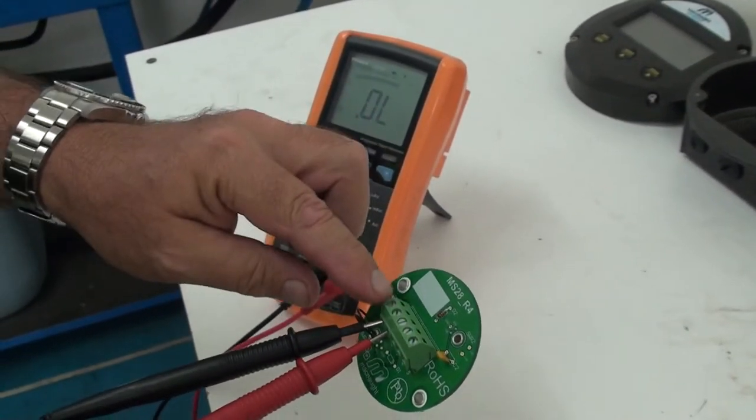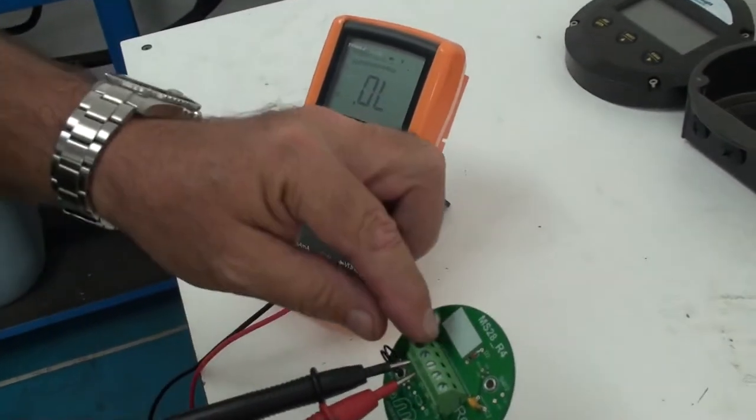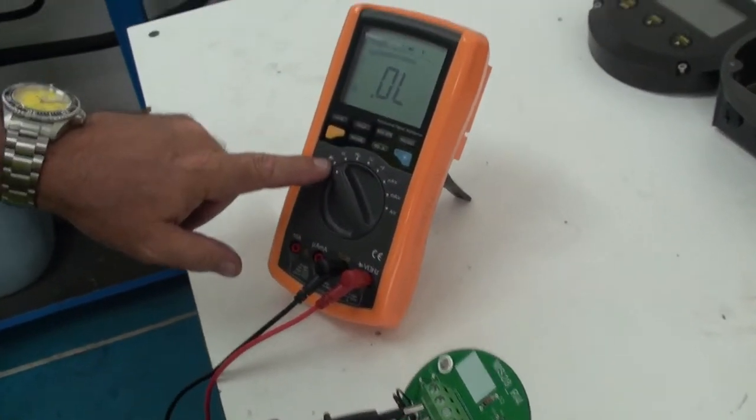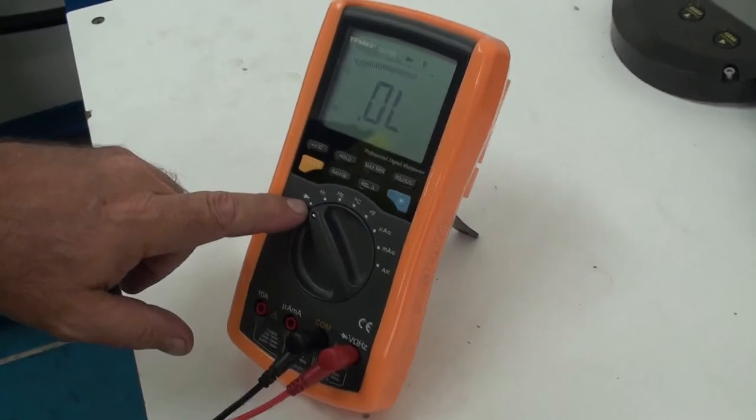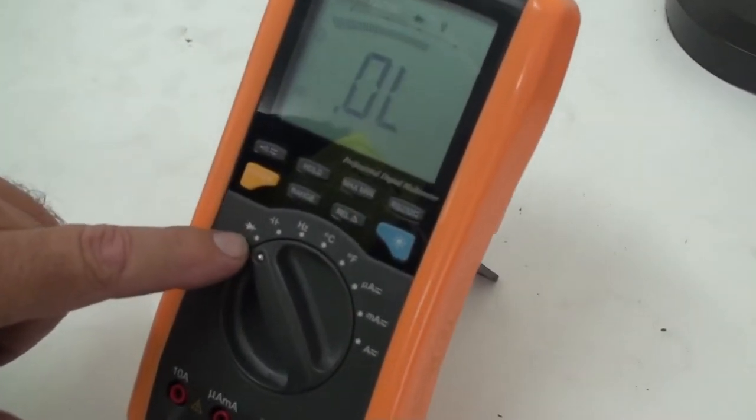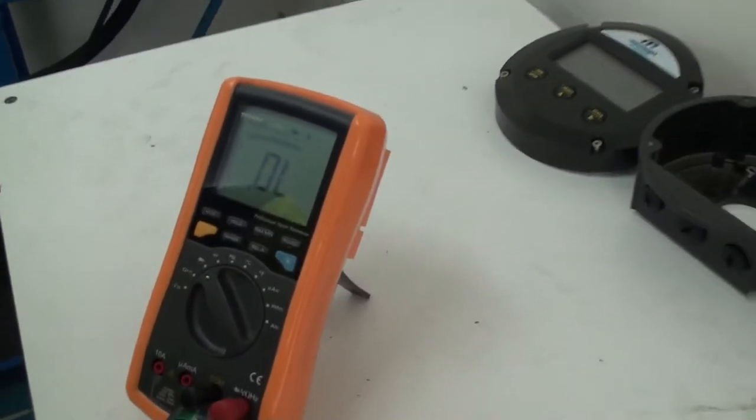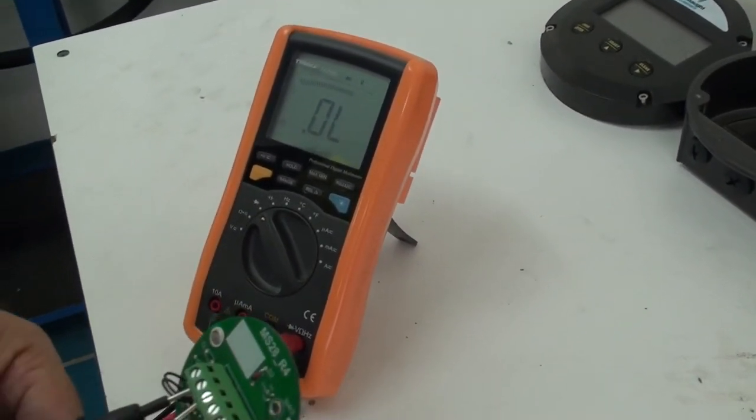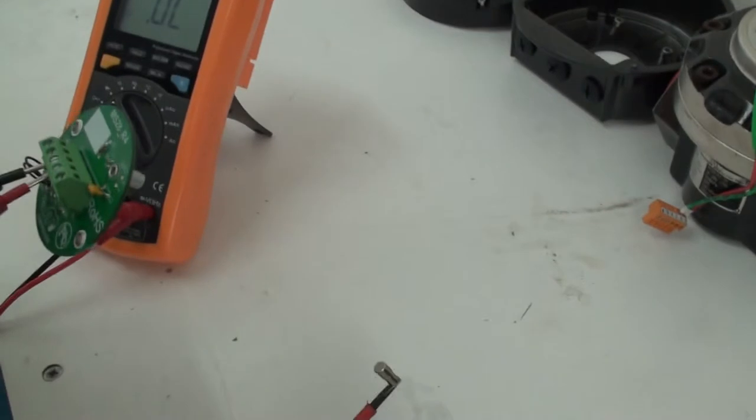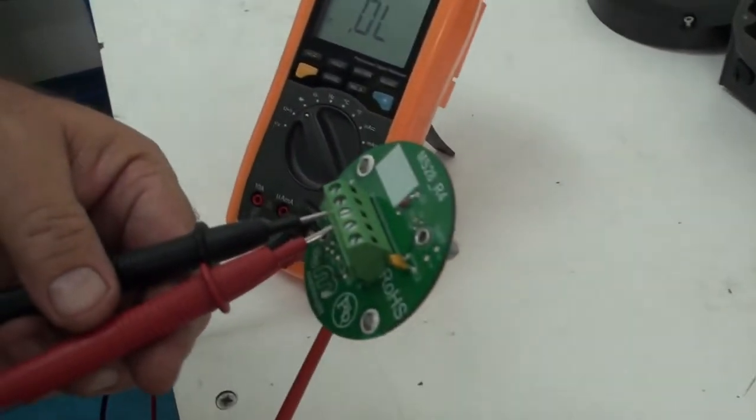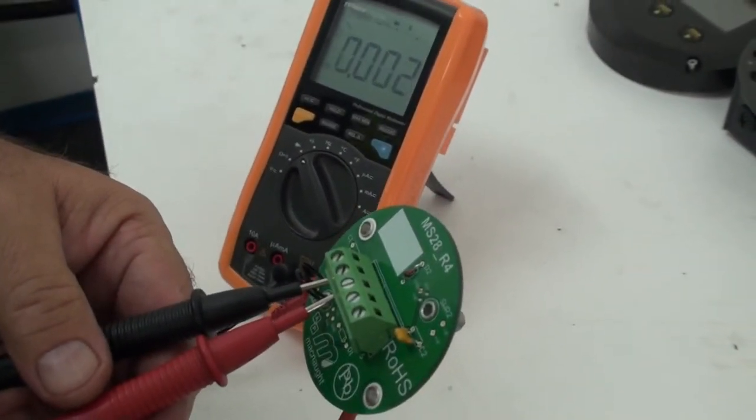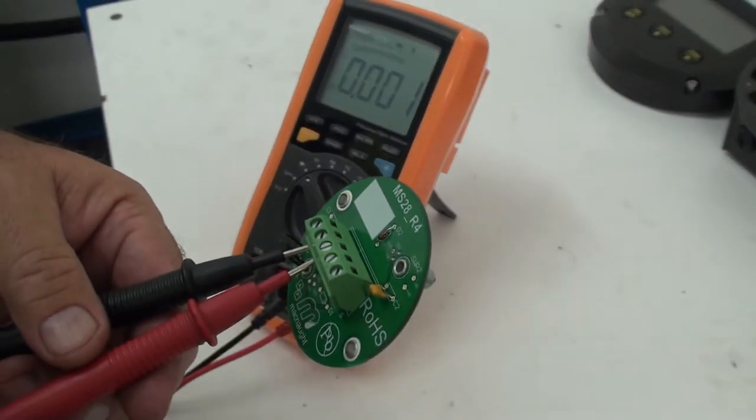So what I've done is I've put my multimeter probes into terminals 1 and 2. I've set my multimeter onto continuity, and it's open circuit at the moment. I then have a magnet on the end of my screwdriver, and when I wave that magnet underneath the sensor, you can see it goes short circuit.